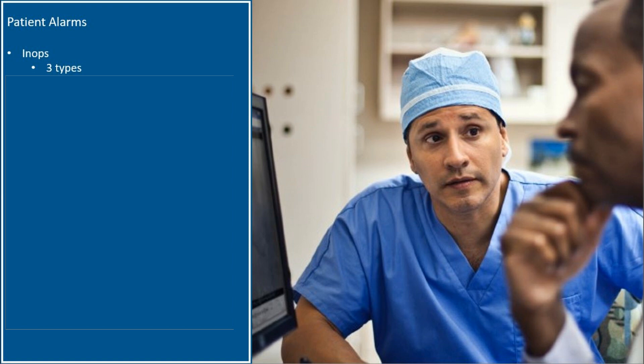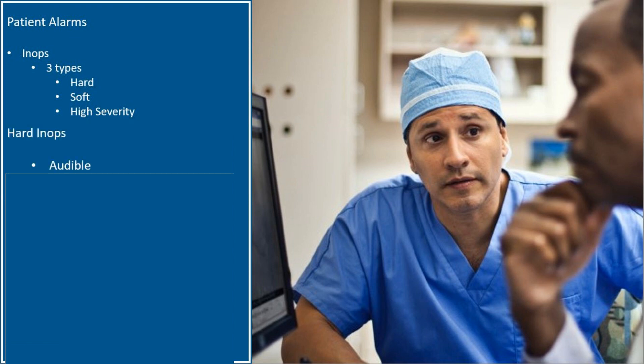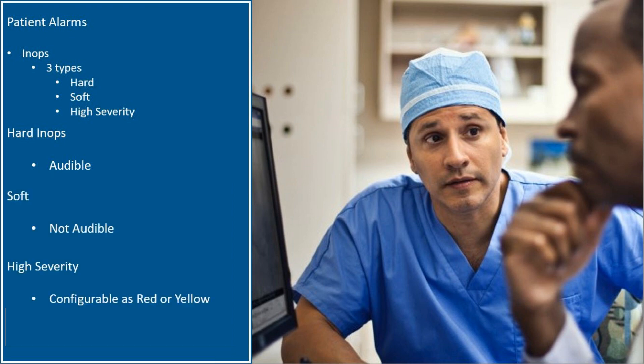There are three types of in-op alarms: hard, soft, and high severity. All three types indicate an inoperative condition. Hard in-op alarms are indicated audibly while soft in-ops are not. High severity in-ops can be configured as a red or yellow alarm and they will show in the banner with two or three exclamation points.